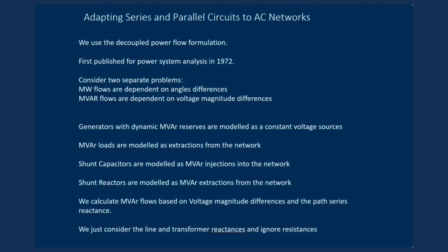The megavar loads are modeled as extractions from the network. Shunt capacitors are modeled as megavar injections to the network, and shunt reactors are modeled as megavar extractions from the network. We calculate megavar flows based upon voltage magnitude differences and the path series reactance. In this analysis, we just consider the reactance, the series reactance of the lines and transformers, and we ignore the resistance elements. For transmission networks, the ratio of the reactances to the resistances is very large, typically 10 or greater.